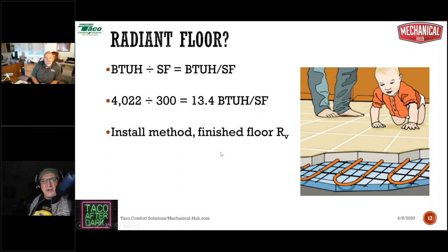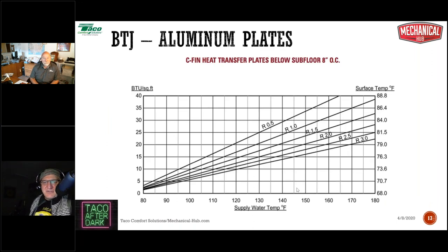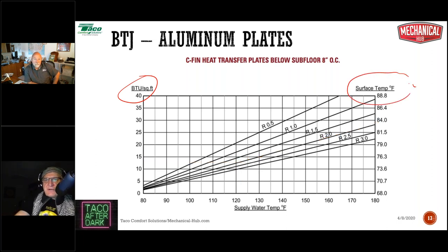Let's now go to our output chart. I think this one is from Mr. Pex, but pretty much every radiant manufacturer has something like this. It's an output chart, and in this case, it's between the floor joists. BTJ stands for between the floor joists with aluminum heat emission plates. These are heat transfer plates below the subfloor with tubing 8 inches on center. Over on the left-hand side of the chart, you see your BTU per square foot load. Over on the right-hand side is our surface temperature.